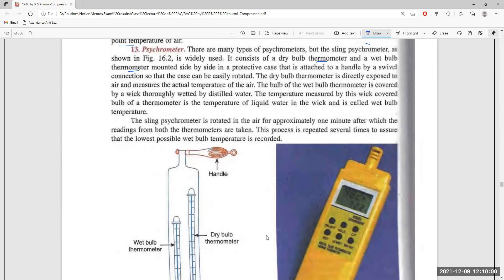The sling psychrometer is rotated in the air for a period of time, after which readings from both thermometers are recorded. Because it is rotated in the atmosphere, it has full exposure everywhere. This process is repeated to ensure that the least possible wet bulb temperature is recorded.